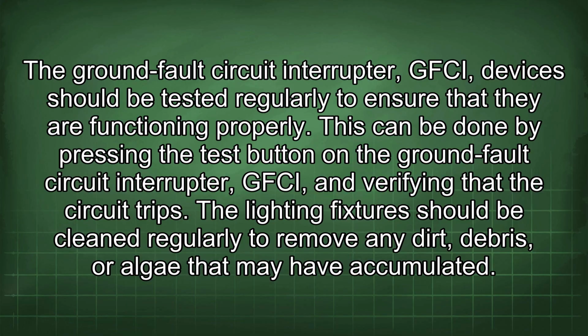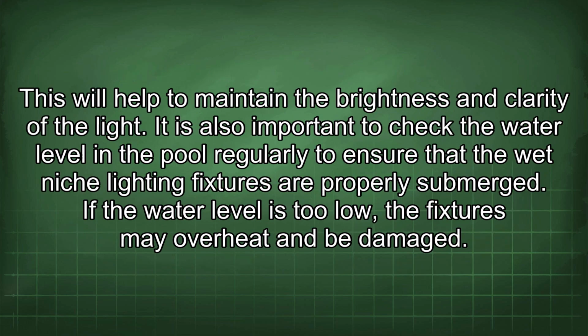circuit trips. The lighting fixture should be cleaned regularly to remove any dirt, debris, or algae that may have accumulated. This will help to maintain the brightness and clarity of the light. It is also important to check the water level in the pool regularly to ensure that the wet niche lighting fixtures are properly submerged. If the water level is too low, the fixtures may overheat and be damaged.